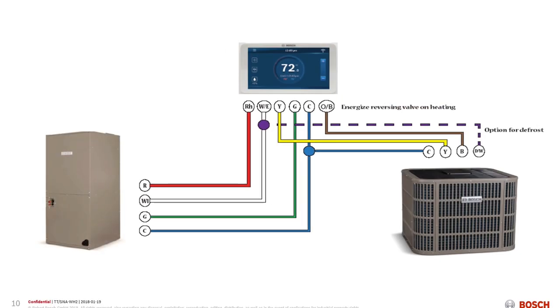When you're wiring up my outside heat pump to the air handler, let's use a thermostat that we would call simple. This particular thermostat must be a heat pump thermostat. It is going to be a dedicated C thermostat and not a power robbing thermostat. In the simple process, we don't want a thermostat that has thinking logic behind it. Again, let's use a simple thermostat. If you're only going to use this in the air conditioning mode, I just need 2 wires running out to the condensing unit. Give me a Y, give me a C, I'll work as an air conditioning system. If we're going to hook it up as a heat pump, add to those 2 wires a B, which operates the reversing valve, and also a W wire for defrost.